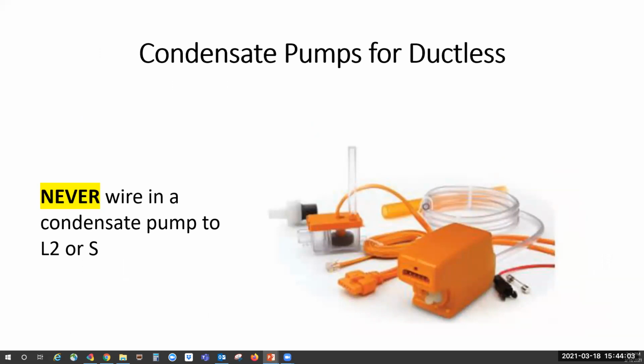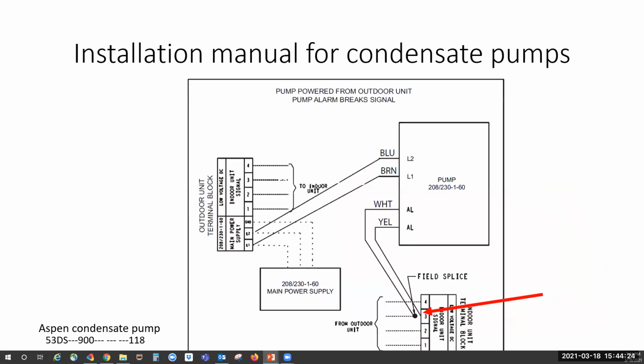Condensate pumps for ductless. Never wire in a ductless or condensate pump on L2 and S. If you have a condensate pump and communication issues, you want to verify the pump is obviously working and functioning correctly. And these little pumps are notorious for getting plugged up. The installation manual for these pumps is written for all brands of ductless. Therefore, they are universal. But on Carrier, Bryant, we do not break the signal wire. We always break L1.